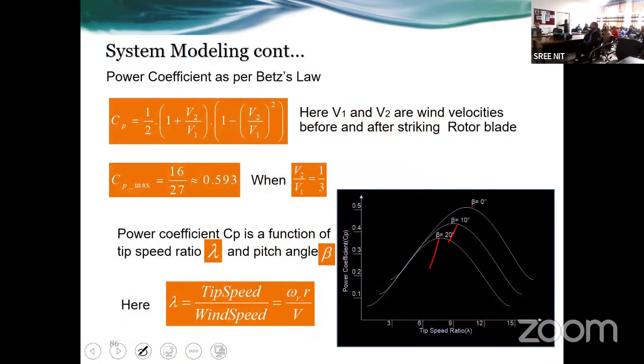For different pitching angles, beta at 0 degrees gives maximum power, 10 degrees slightly reduced power, and 20 degrees further reduced power. So there are different angles: yaw control and pitch control. Pitch control is within the blades. Yaw control is rotating the whole set of blades. This is yaw and this is pitching, meaning changing the slight wings of the blades. Pitching is there because sometimes you need to curtail the output power of the turbine, as the wind speed may be too high. Pitching is required to maintain the output power within the rated, permissible limits of the turbine. And yaw control is sometimes required when the wind speeds are so dangerous that they can damage the wind turbine.